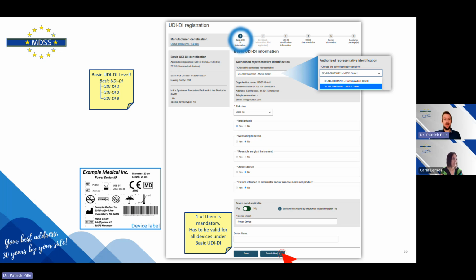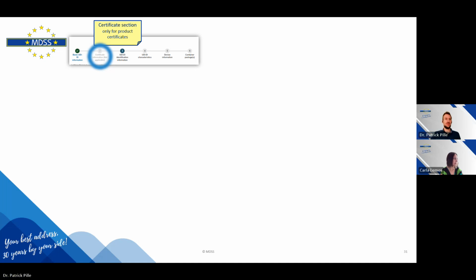Once we solve that hurdle, we come then to step 2. It is grayed out here because we are registering, in this example, a Class 2A device. And interestingly enough, certificate information, so the notified body at least, only has to be registered for devices that require a product certificate and not the usual quality management system certificate. So we are talking about high-risk class devices, for example, Class 2B implantable that are not well-established technologies, and Class 3 devices. The same goes for IVDR. We are just registering Class 2A here, so this step is just skipped.